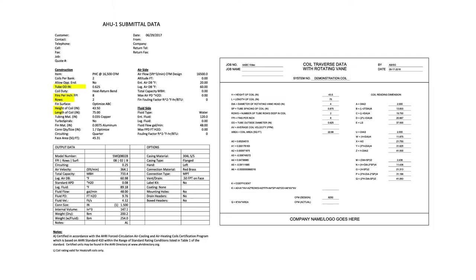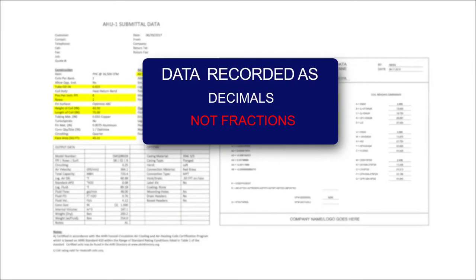To start the process, submittal data is recorded into the coil traverse data with rotating vane form, which is then verified in the field. This AHU-1 submittal data was provided and used to input the highlighted measurements into the form. The data is recorded as decimals and not fractions, using the inch-pound unit of measure.